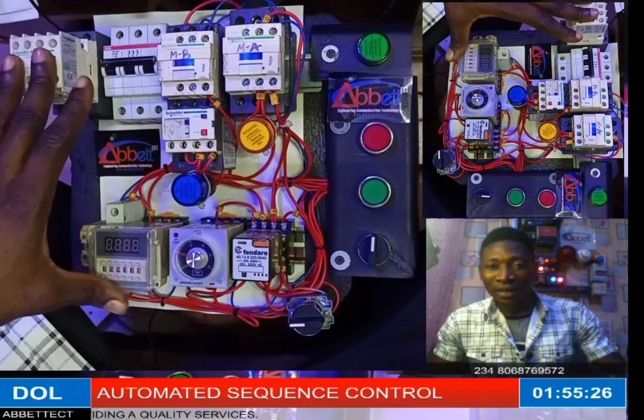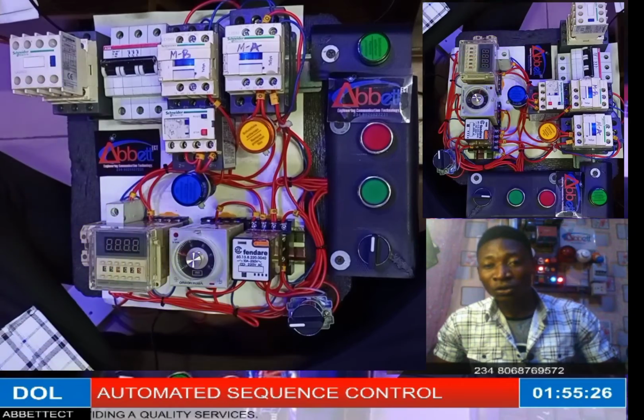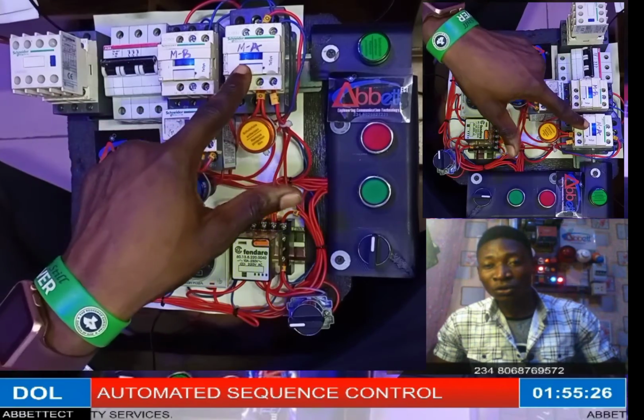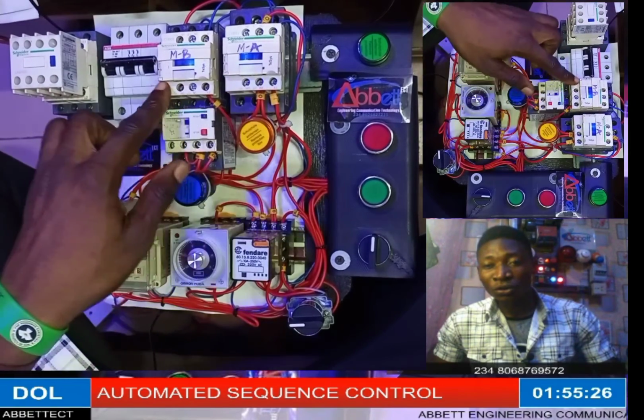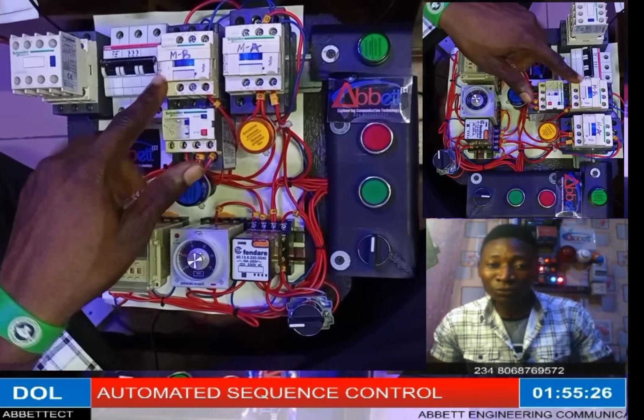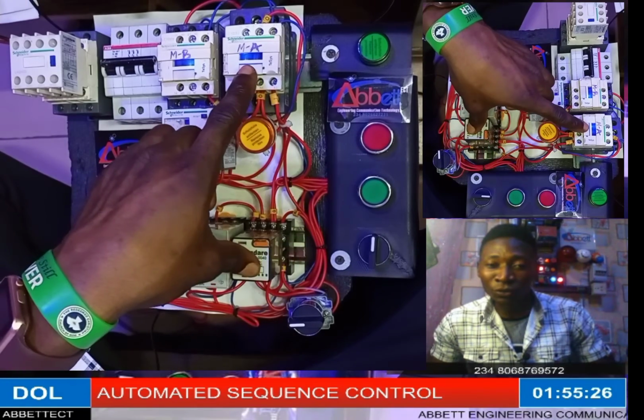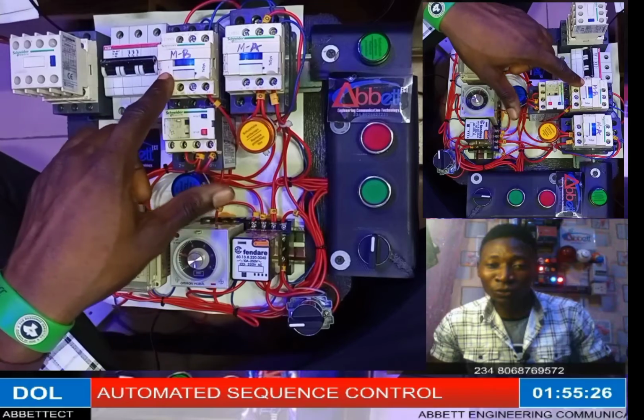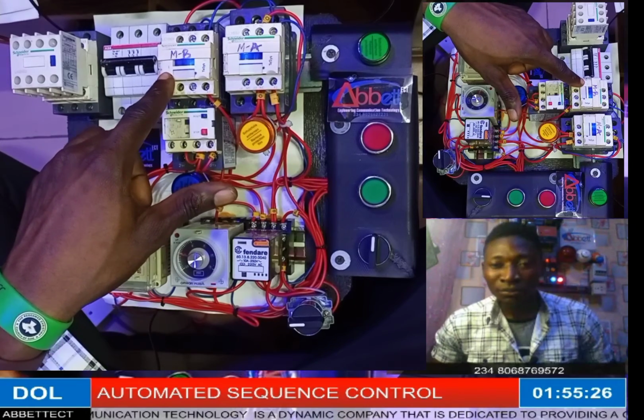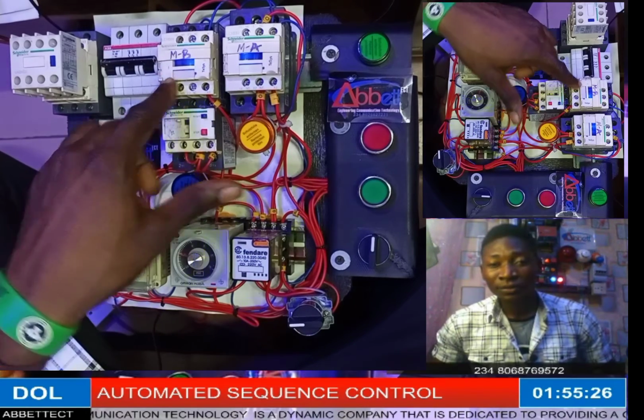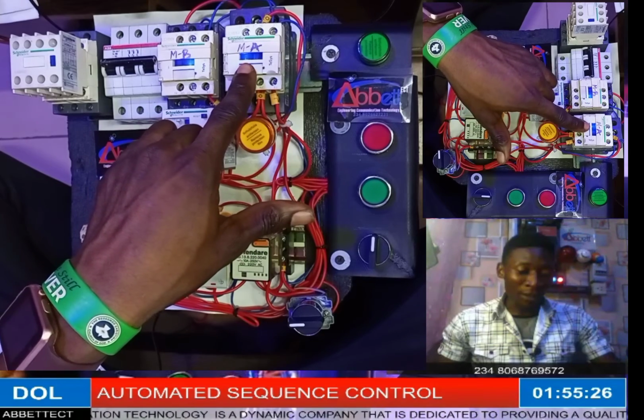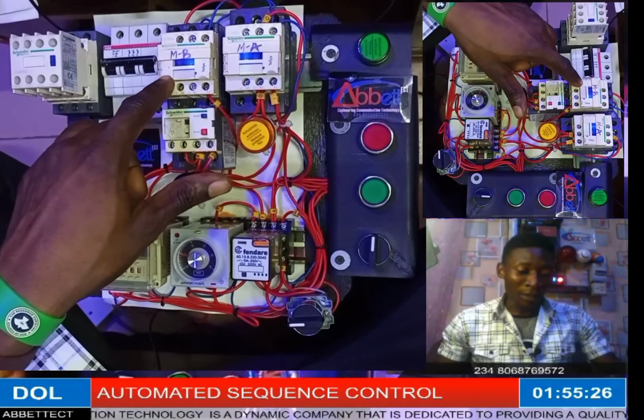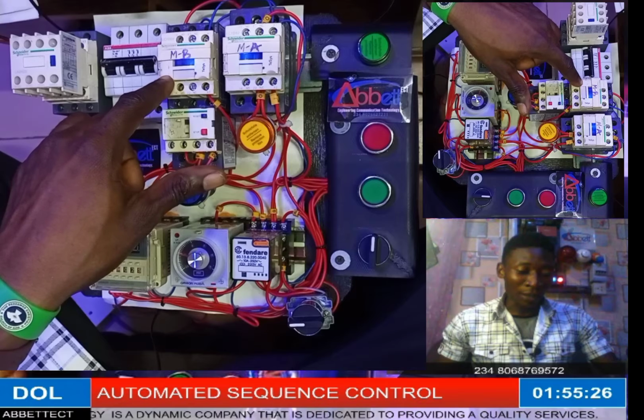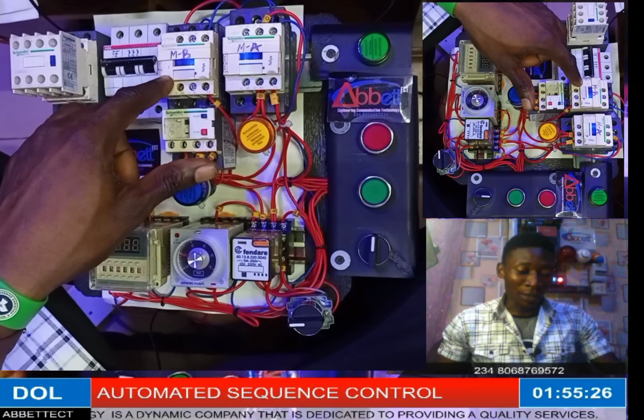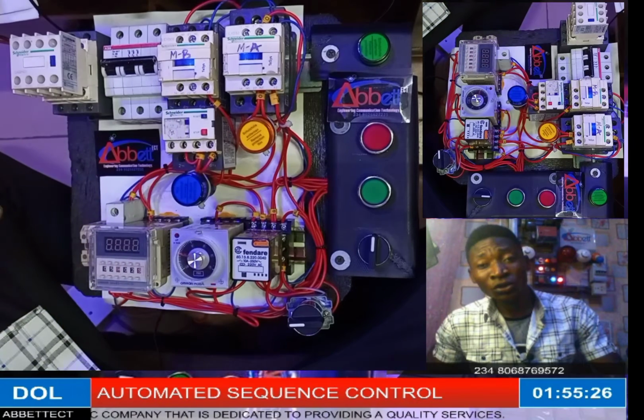The interlock of this system is defined as: if motor A is not running, motor B will never come up. If you did not start motor A, if motor A is not running, motor B will never start. If you start motor A and it's running, that's when you can start motor B and it will respond to your calling.